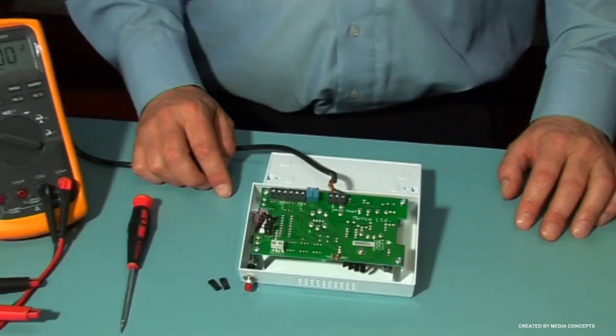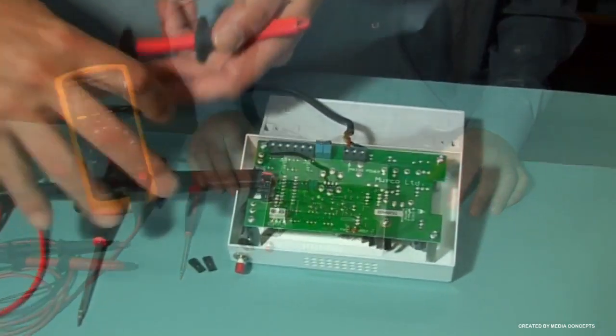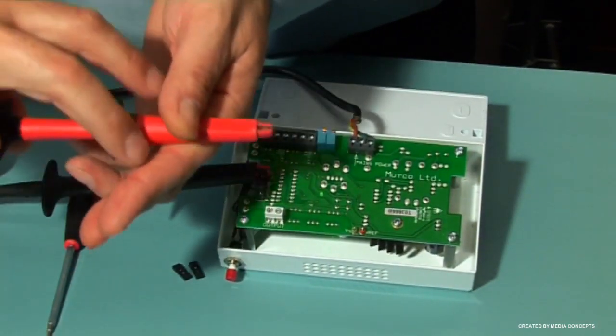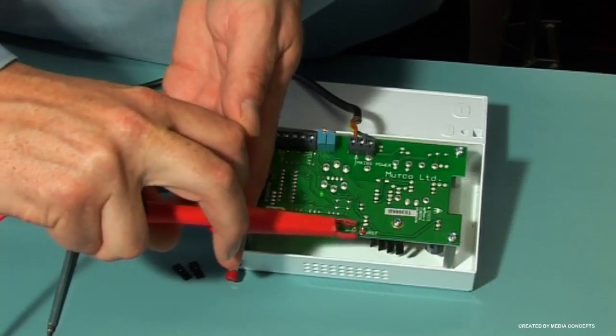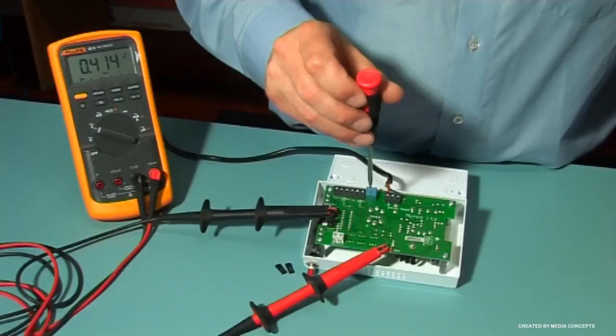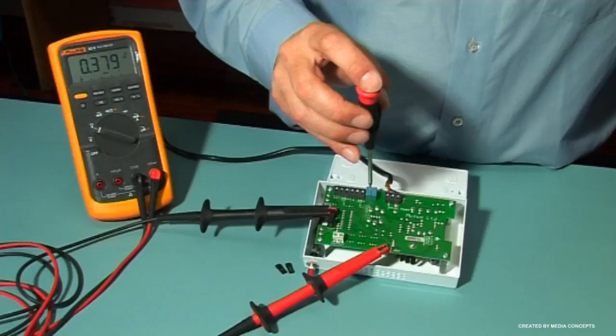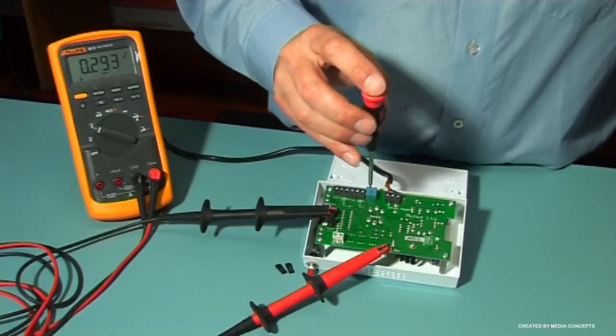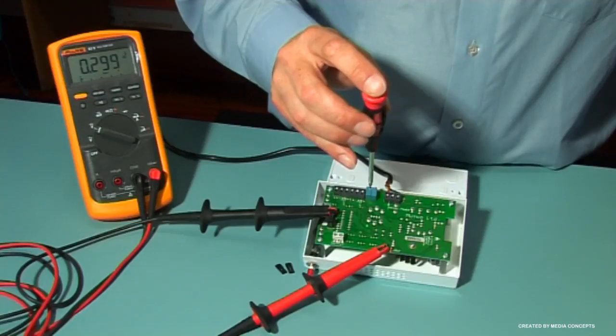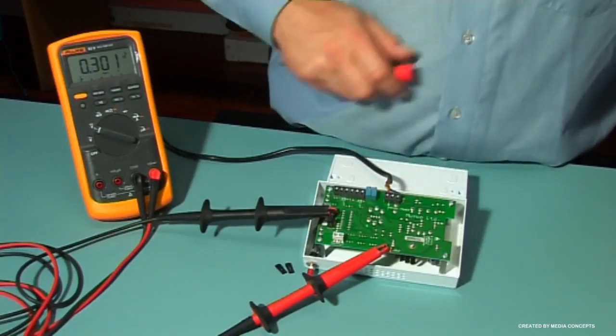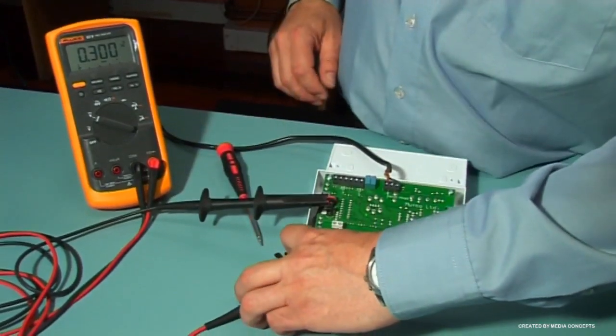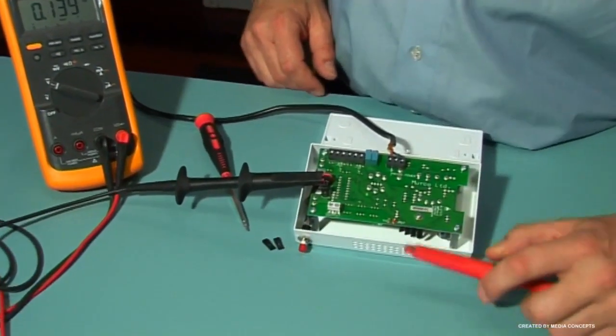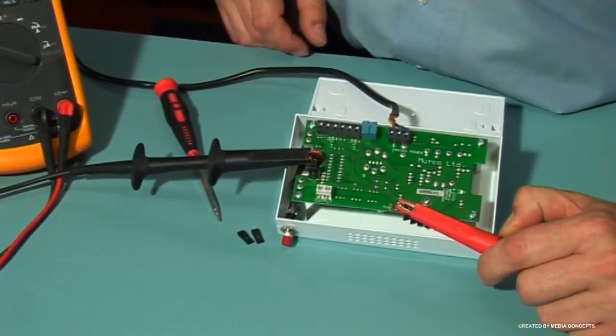So with your voltage meter, between 0V and Vs, check and record the standby voltage. If different to the rating label factory voltage, then adjust P1 to the standby voltage, which is normally 0.3 volts, or as shown on the rating label. Move your positive lead from Vs to Vref and adjust P2 to the alarm voltage as shown on the label.